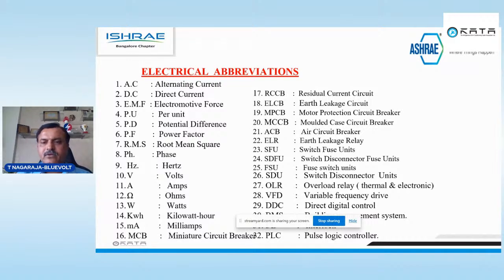Nowadays, electronic overload relay is widely used because a thermal relay's tripping time will be more, because it has to get heated up before tripping. It will take almost 60 to 90 seconds. Our electronic relays are instant so that we can save breakers and contactors from getting burned.